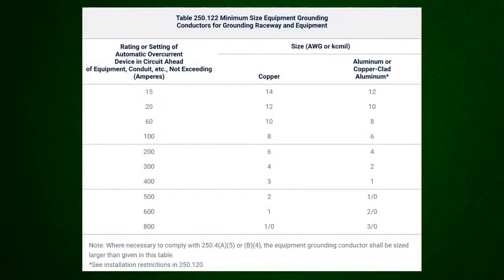Dude, to me, right away, the part that is like a dog whistle for me, that drives me crazy, is him saying you're not paralleling the same way as ungrounded conductors. What do you think this table's based off of? Well, first of all, let me just say this. Each one of those conduits that you go into, you got to pull in each one of them an equipment ground, okay, in order to get the fault current path back. And it's based on the size of the overcurrent protection device. And 100%. So why he's saying you're taking a bunch of smaller conductors and doing this, I don't even know what the heck he's talking about.